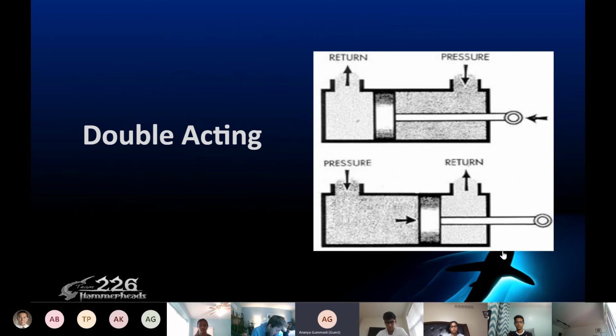Both of these valves that I just talked about, the single action and the double action valves, work using solenoids where you apply power to a solenoid on an air valve and the valve then opens. So for a single action valve, programming can just use a true or false method so that when applied power is true, the valve is opened. But the double action valve, though, is more complicated.